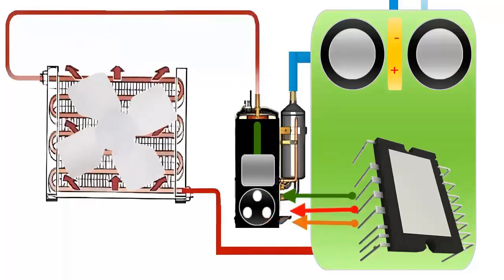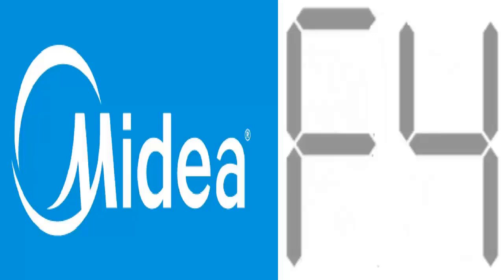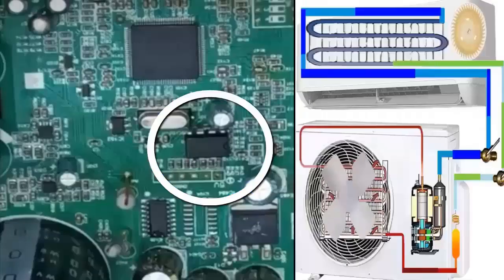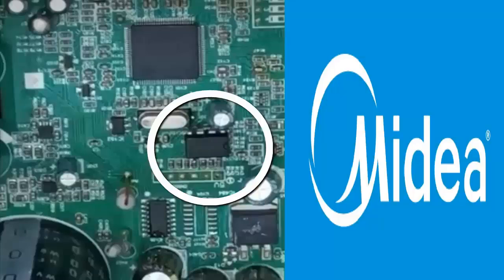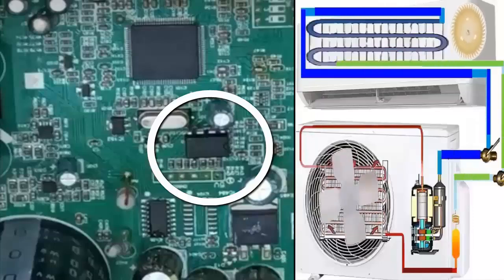Error code F4 indicates issues with the EEPROM memory on the electronic board, located in the outdoor unit, possibly due to electrical failures. The diagnostics for this issue will be covered at the end of the video.